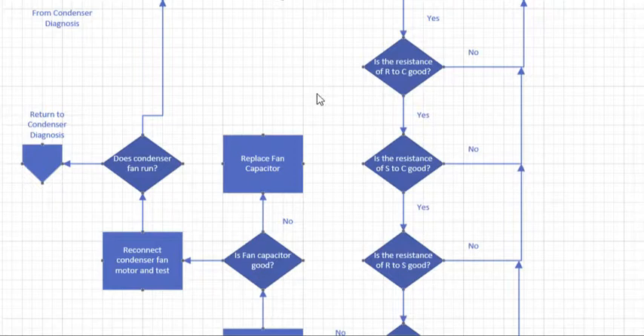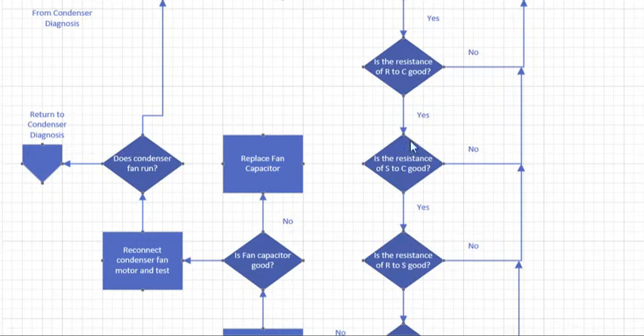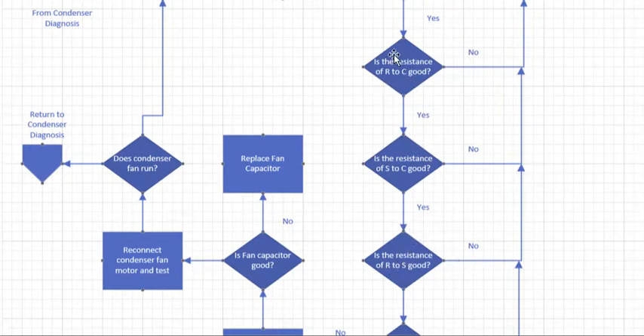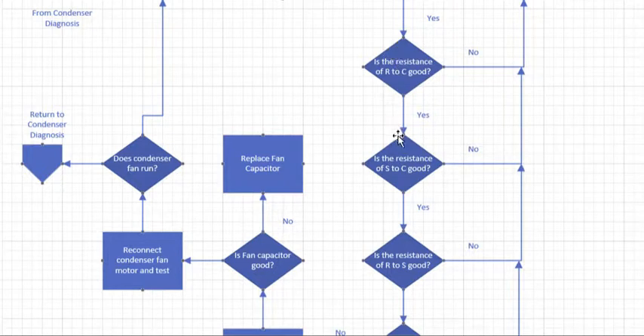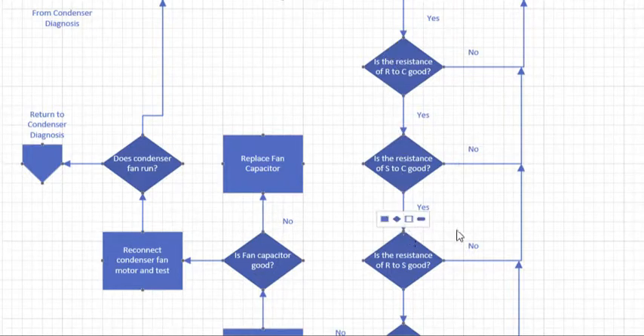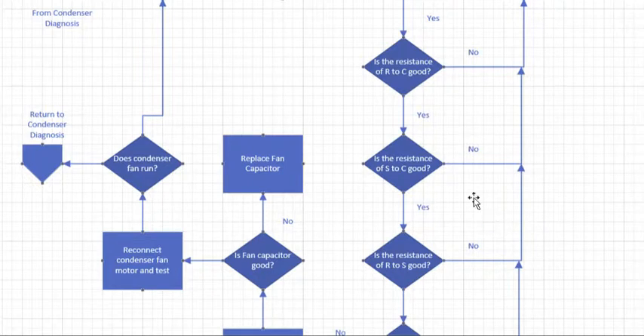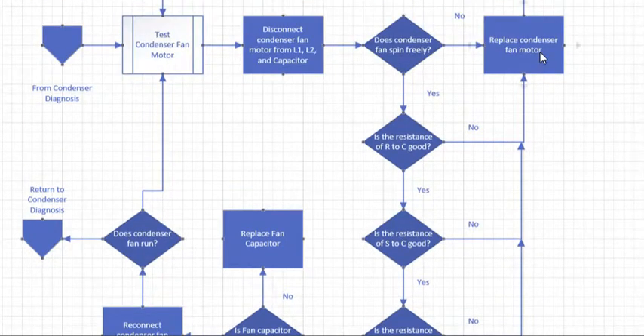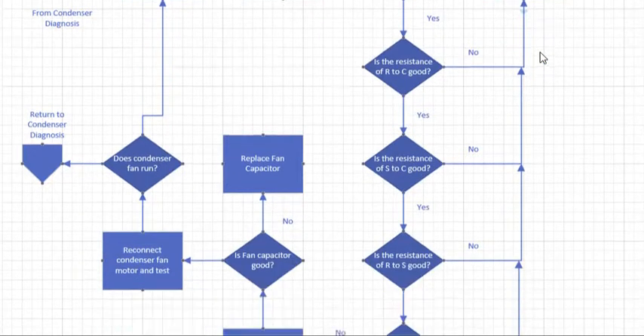If R to C has a number, S to C has a number, then R to S should be the sum of both the other numbers and you want to check it. Your R to S reading should be the R to C and the C to S added together or very close to it. If any of these readings are bad, replace the condenser fan motor.